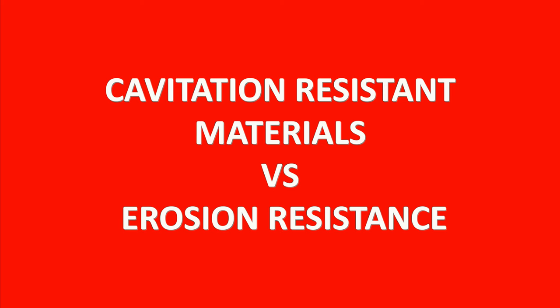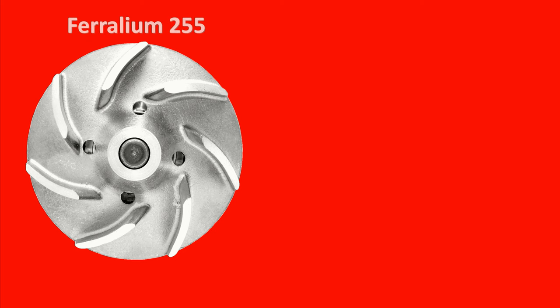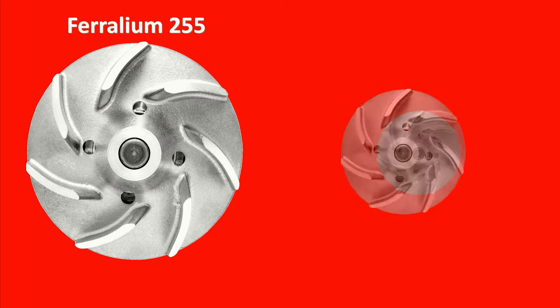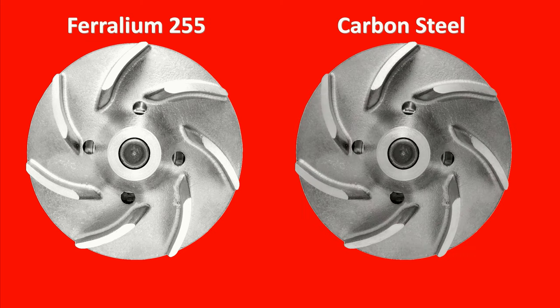Tip number three: focus on cavitation-resistant materials. Studies have shown that some materials are more resistant to cavitation erosion than others. Invest in the right materials if cavitation damage is unavoidable in your system. For example, Ferralium 255 has much better cavitation resistance than cast carbon steel — so choose your impeller material wisely.